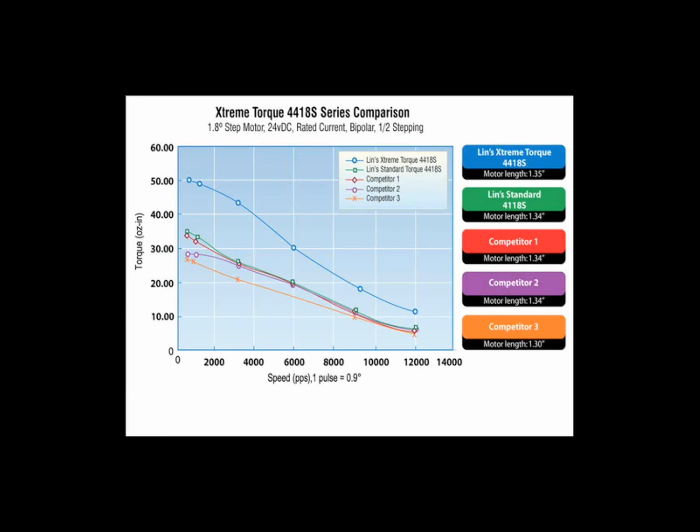And at the curve here, you'll see that the green, orange, red and purple ones are the torque speed curves of the standard motor industry, including our previous designs. Now, we came out with a new design that was able to increase torque by as much as 35% across most of the speed range, and even into the higher ranges, you're getting more torque. So if the application requires more torque throughout the entire speed range, you can go to a completely different design.